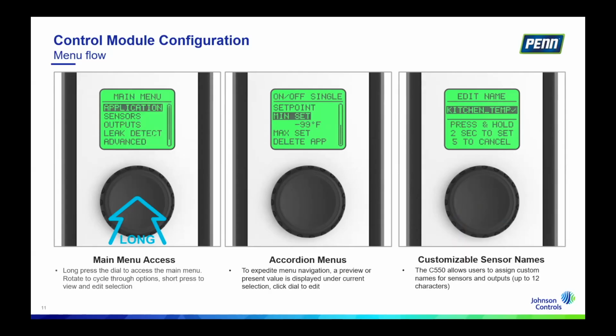The other thing that you'll find, and hopefully you'll find this intuitive and helpful with the menu, at least in viewing it and setting it up, is these accordion menus in the middle. That means if there is a set point or an adjustment already made in the menu, it'll accordion out and show you that it's already been set. You can see on the left-hand side that the menu is relatively short. It starts with the application, and I'll talk about that in a minute. Then the sensors, then the outputs, and then leak detect. You will only use this if you're using the A2L functionality.